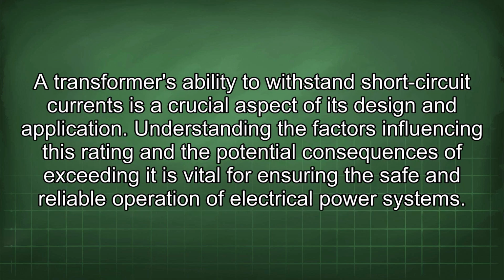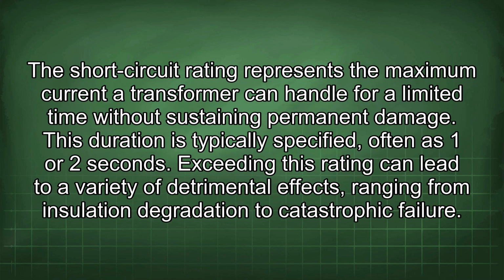A transformer's ability to withstand short circuit currents is a crucial aspect of its design and application. Understanding the factors influencing this rating and the potential consequences of exceeding it is vital for ensuring the safe and reliable operation of electrical power systems. The short circuit rating represents the maximum current a transformer can handle for a limited time without sustaining permanent damage. This duration is typically specified, often as 1 or 2 seconds. Exceeding this rating can lead to a variety of detrimental effects, ranging from insulation degradation to catastrophic failure.